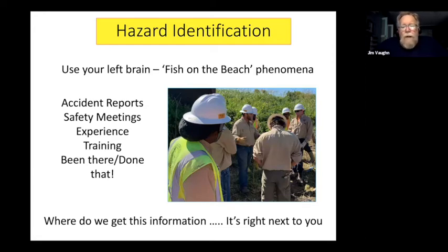I'm going to tell you one that I've seen probably a half a dozen times, and it was back from the manual ground rod driver days, the pipe with the weight that's on the end of it. We hardly ever use these anymore, but what I consistently found was that some over aggressive, really excited helper was going to show how fast he could get that ground rod in the ground. And you know what happened? The ground rod driver came off the end of the rod, and somehow your hand ends up over the ground rod, between the ground rod and the ground rod driver.